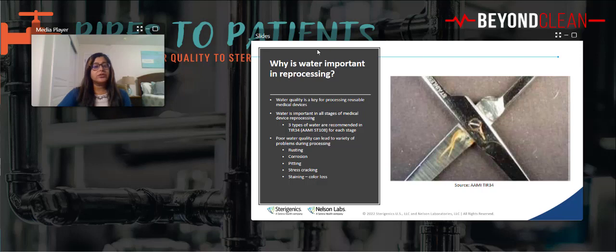Now, poor quality water, you see a picture here. I'm sure you've seen this in your facilities all the time. I have seen it in my facilities on dunnage devices, right? Those are devices that just go in with the validation devices that we put in the washer to simulate a full load. They never get changed. They just sit in there and get processed over and over, and they must be processed 500 times. Once they break is when we get new ones. So they do break, they do get rusted, they do get discolored. I will go over some pictures of our dunnage devices that we've seen over maybe 50 or 100 washes that we have to replace all the time, even after monitoring our water quality systems, right?